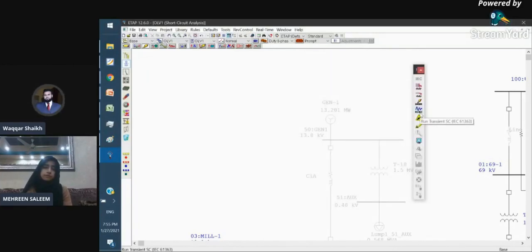Here we have IEC 61363. So if you are working on a marine network, you should run IEC 61363 short circuit analysis, not 60909 or other standard analyses. Those first types of simulations are only for ground-based systems, normal distribution networks connected with the grid or local generation having proper earth grounding. But for marine installations, IEC 61363 is the applicable standard for conducting marine-based short-circuit simulations.